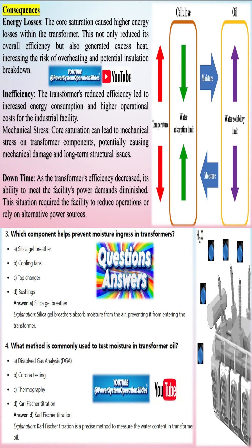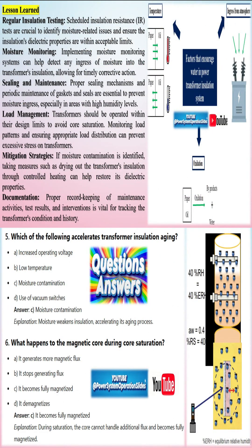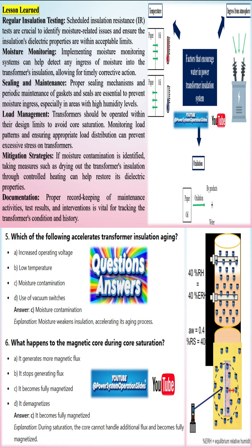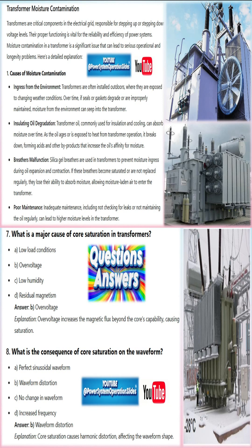Most of the water in a transformer resides in the cellulose. During operation, influenced by varying loads and temperatures, water migrates between the oil and cellulose. Elevated operating temperatures can temporarily double the water content in the oil. Even minimal water presence in the solid insulation accelerates aging, reduces the transformer's permissible hotspot temperature, and heightens the risk of bubble formation, which can lead to dielectric failure.